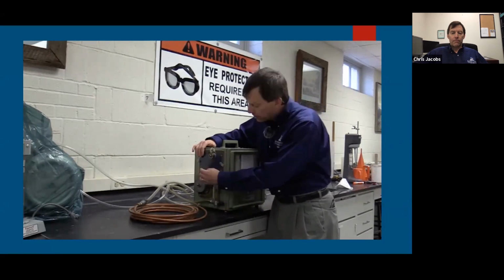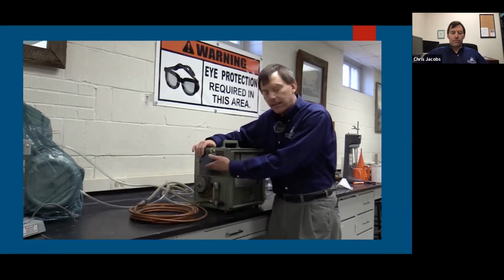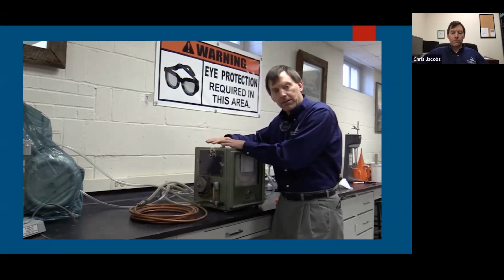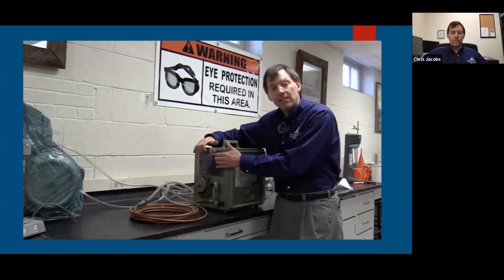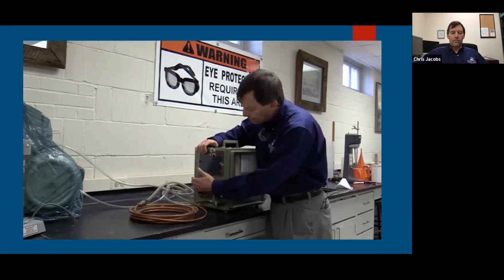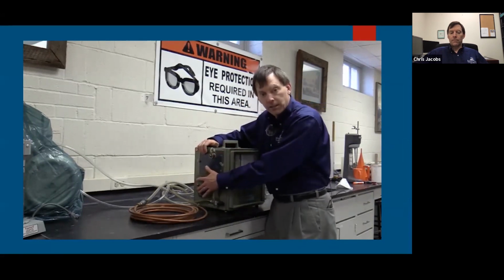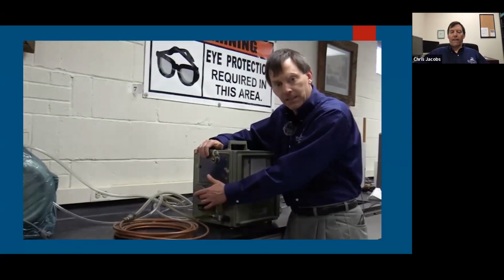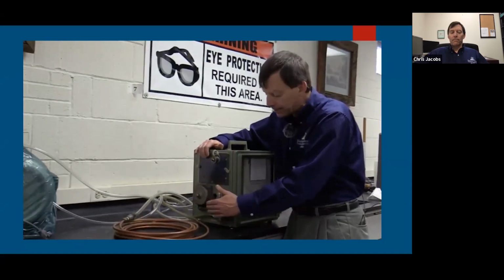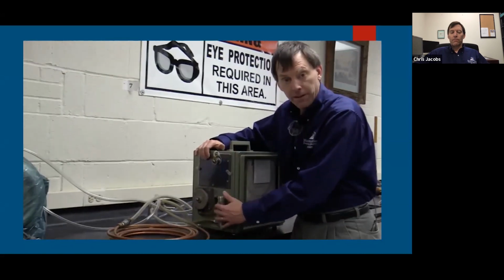The way that it works is it pulls air in through these holes in the bottom, and then there's a grate, and then it works its way into the machine. So we want this to be that nice deep blue color. That means the desiccant is active and ready to be used. This is a selector switch that we're going to use to determine whether we're going to put a high specific gravity gas or a low specific gravity gas. And as you can see, this is the flow meter.